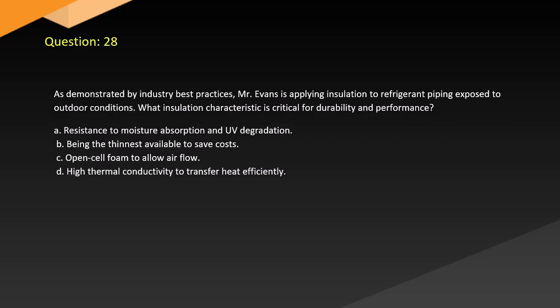Question 28. Demonstrated by industry best practices, Mr. Evans is applying insulation to refrigerant piping exposed to outdoor conditions. What insulation characteristic is critical for durability and performance? A. Resistance to moisture absorption and UV degradation. B. Being the thinnest available to save costs. C. Open cell foam to allow airflow. D. High thermal conductivity to transfer heat efficiently.